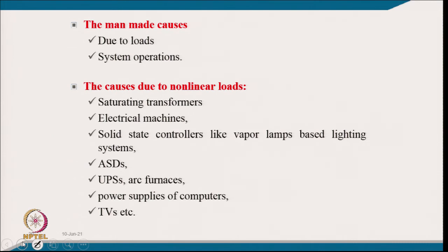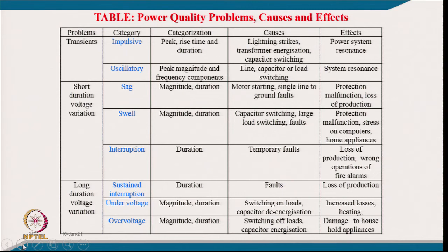A summary table covers power quality problem categories, causes, and effects. Transient problems can be impulsive or oscillatory in nature — quantified by peak rise — and are caused by lightning strokes, transformer energization, or capacitor switching. They cause power system resonance. Oscillatory transients can be quantified by peak or frequency components and are caused by line switching, capacitor switching, or load switching, also causing system resonance.